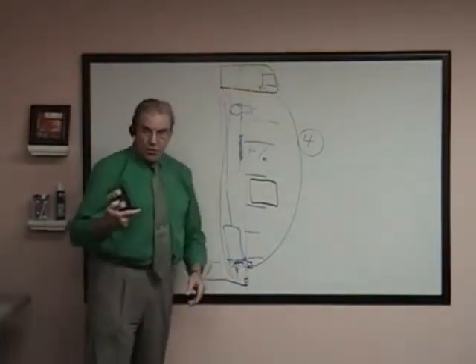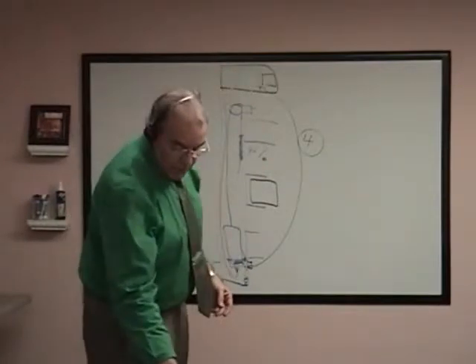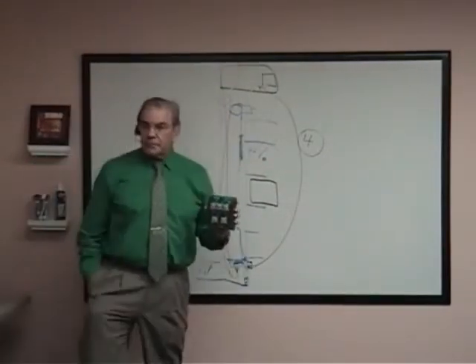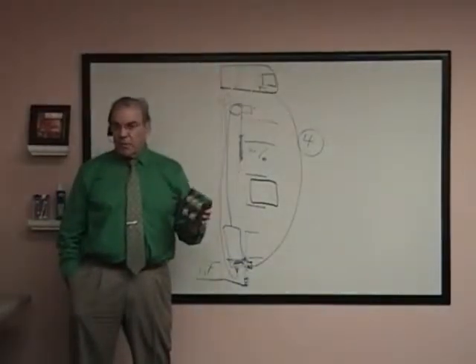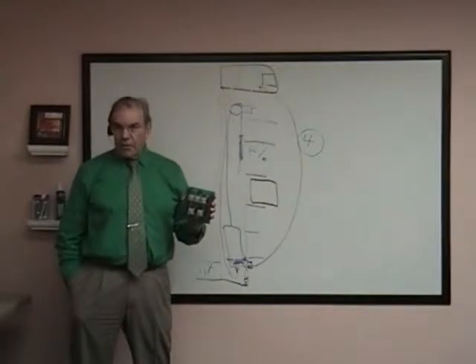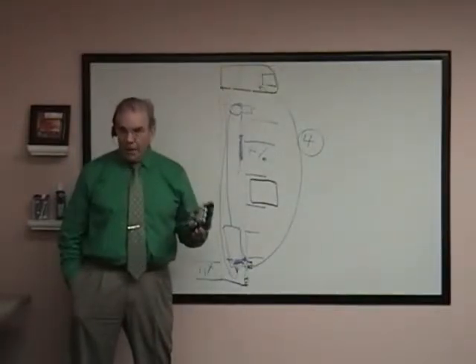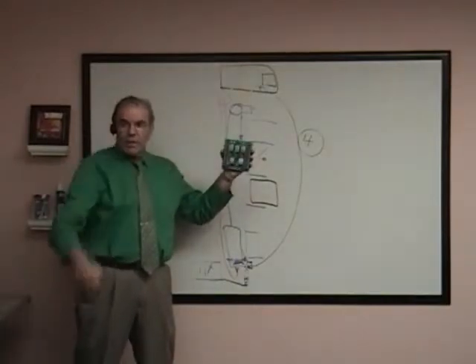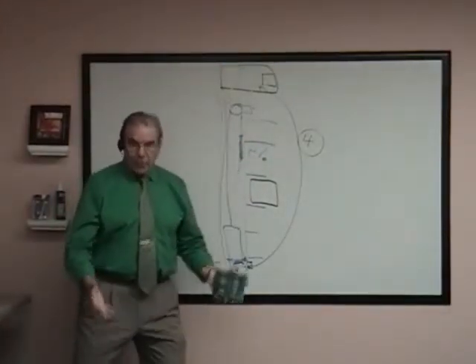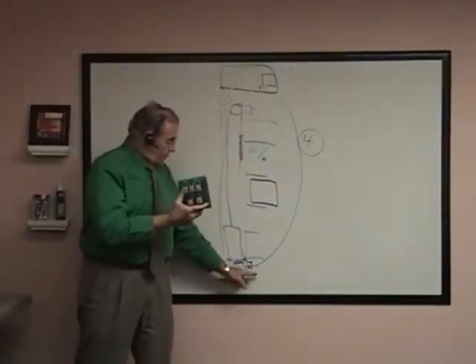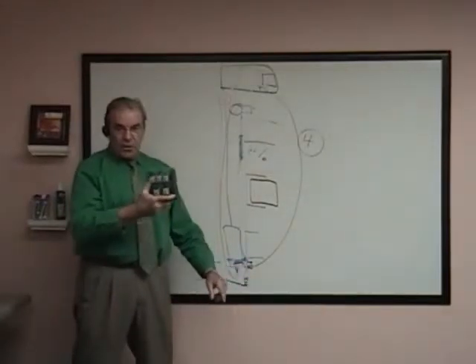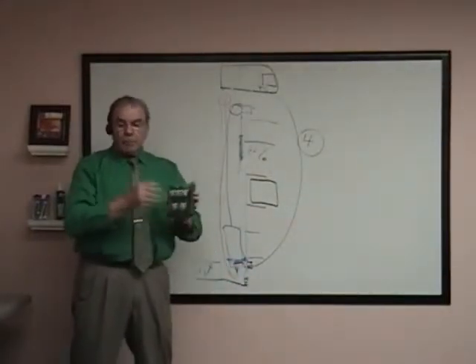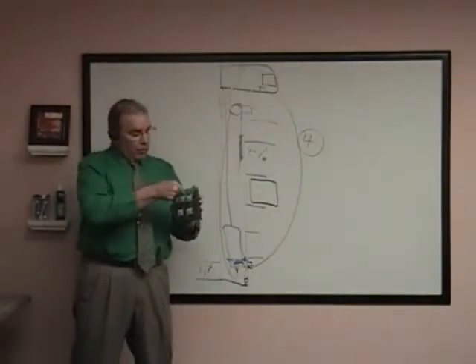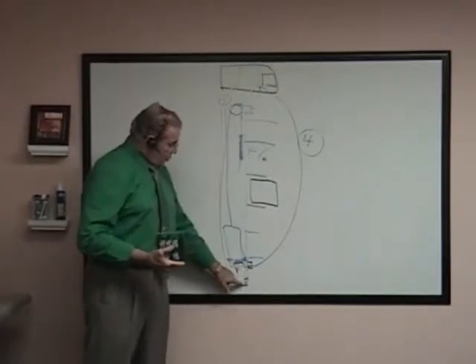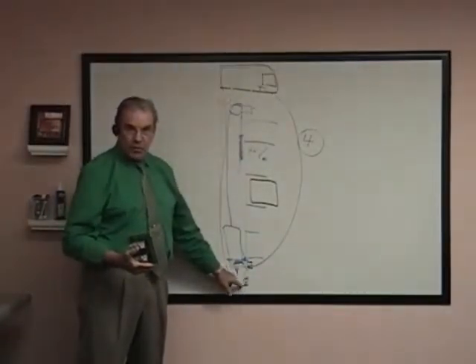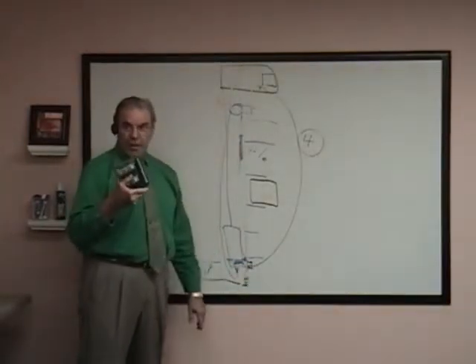And we're going to leave that as an install option. So, and that's the only install option he gets. The automatic reset option is done by moving the jumper? Yeah. Before you install it or after it's installed? It doesn't matter when you move it. In other words, we're going to ship it in the A position, which means manual reset. You have to go to the machine room and pull the switch. Right. That'll drop out everything on the elevator, and when everything comes back up, as long as this doesn't have a signal from the switch down here, from the pit switch, this will stay in a dormant position. Okay. Now, if you move the jumper to the B position, as soon as you remove liquid from the pit, and this switch goes to normal again, this will drop out automatically. Oh, okay.